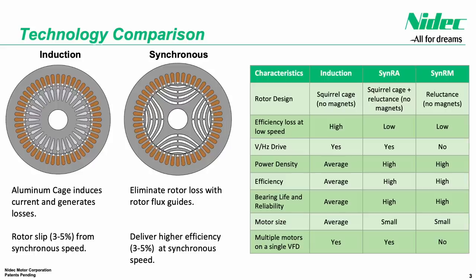Nidec has innovated technology that not only improves peak efficiency but efficiency across the operating range for inverter driven variable torque applications such as pumps, fans, and blowers. This motor technology, referred to as SynRA, stands for Synchronous Reluctance Rotor with Aluminum Cage, and combines the technological benefits of a common induction motor with those of a synchronous reluctance motor in order to deliver the best of both worlds.